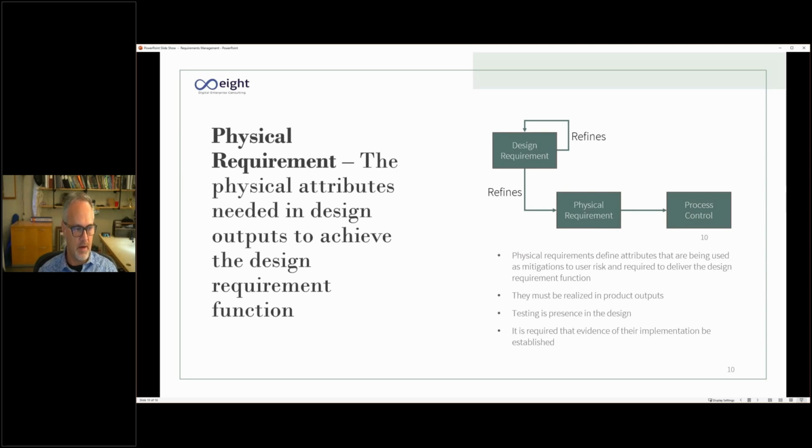And so what I've called these design specifications in the past. That confuses people, because what ends up happening is they think of those as outputs in the design. Really, this is a requirement that something land in the output, that the output is realized. And so we have a print and the material, or we have a part design, and the material that's specified as part of the part is Tyvek, and a certain amount of Tyvek is used. This is a requirement that says before we do the design, what that design needs to entail, right? What needs to be contained in that design. And it might be thicknesses, it might be materials, it could be any specification associated with a part.